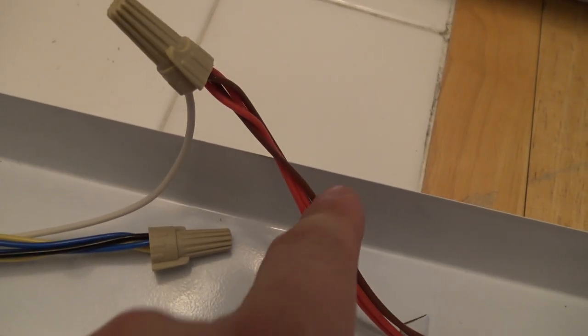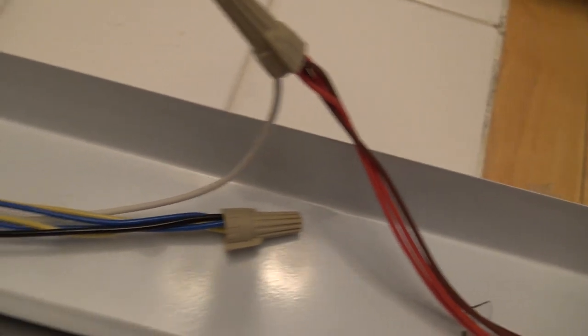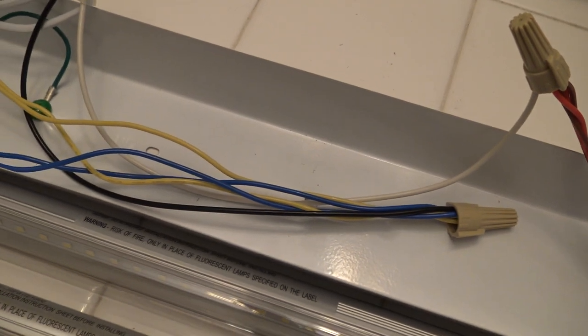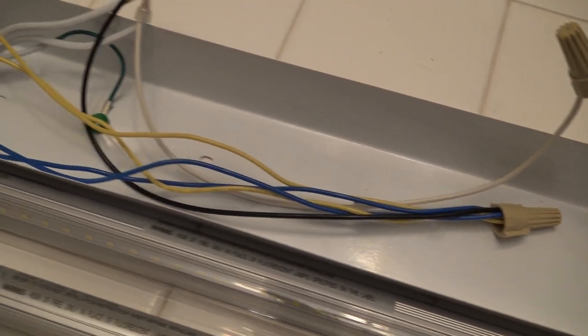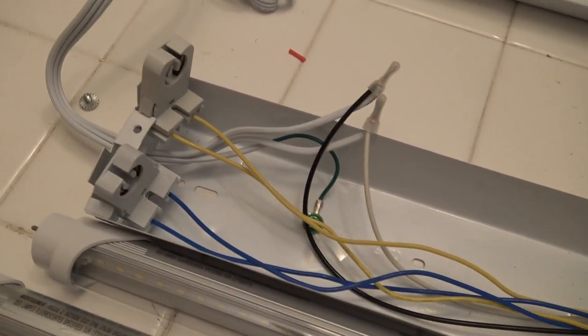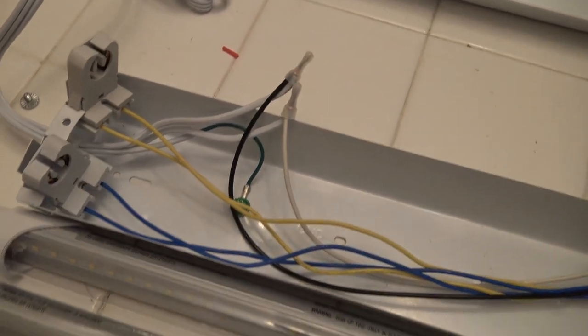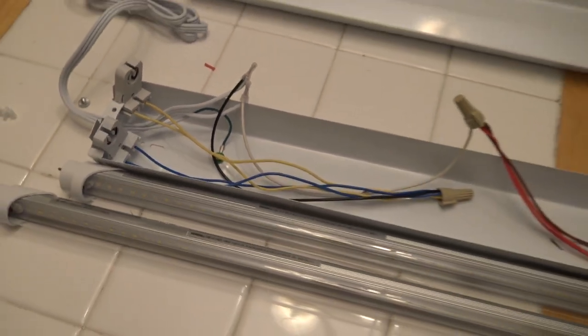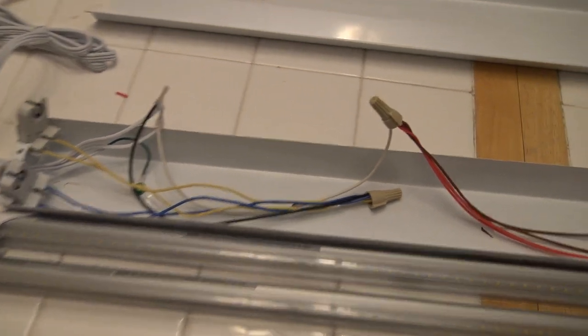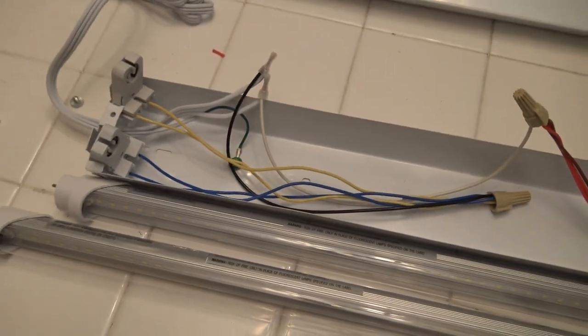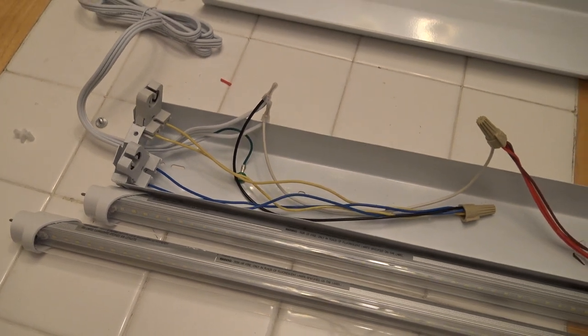And those are all wire nutted to the white. Again, it doesn't matter what color all of the wires from the tombstones are. All that matters is in this two-sided bulb that we're sending the load to one side of the tombstones and the neutral to the other side of the tombstones. So once we've confirmed that all looks good and these wire nuts are nice and snug, let's cover this fixture back up.